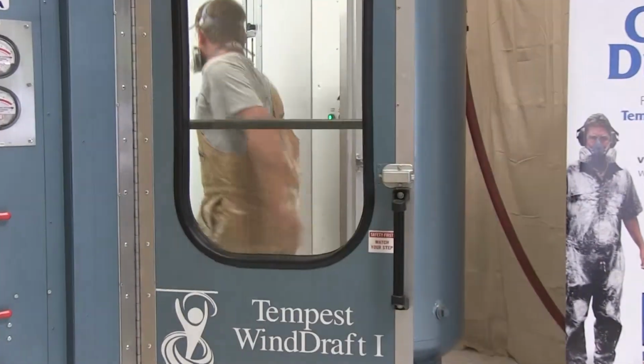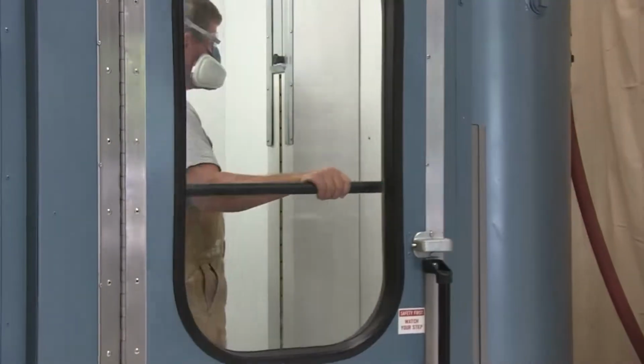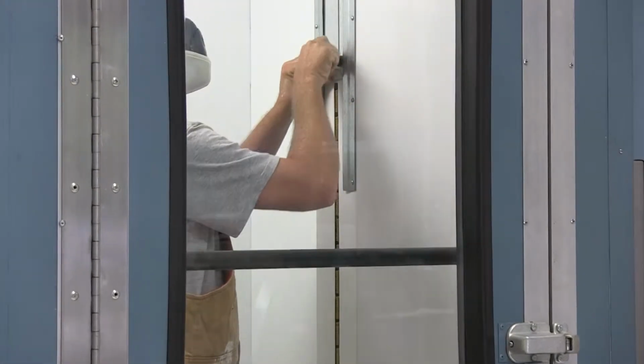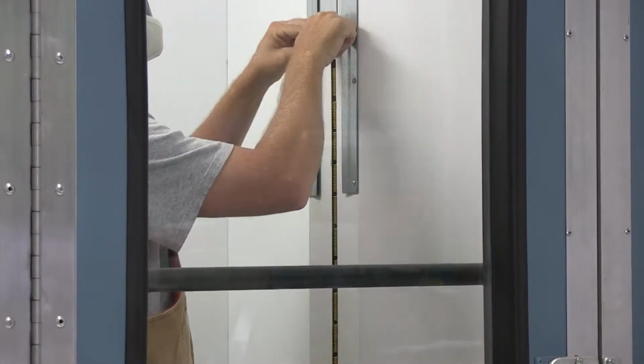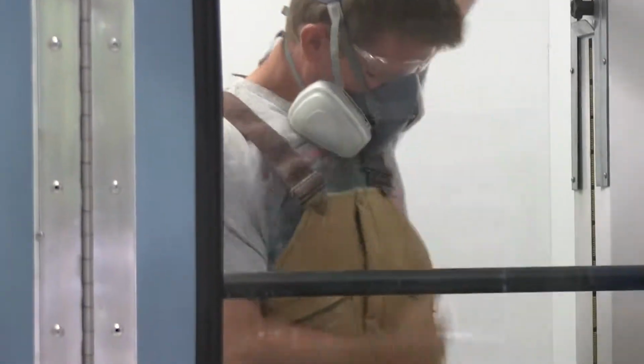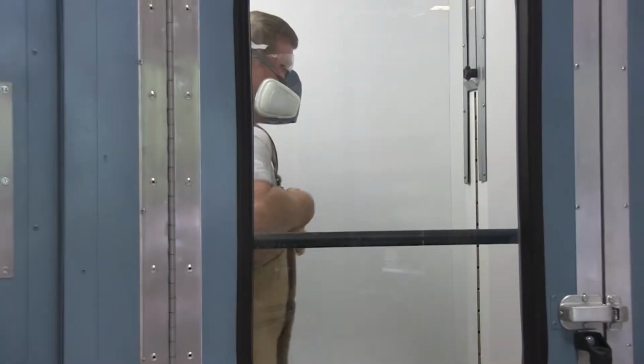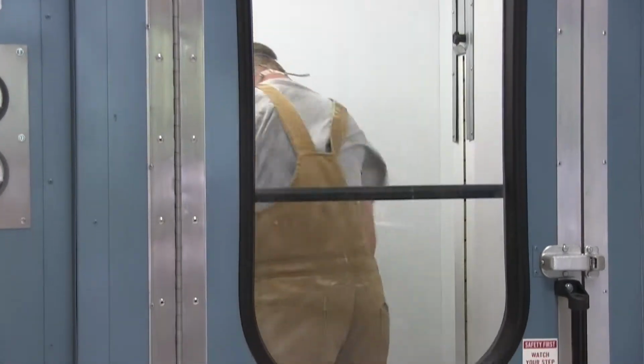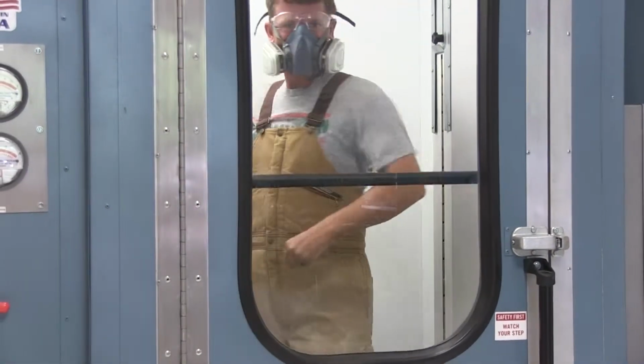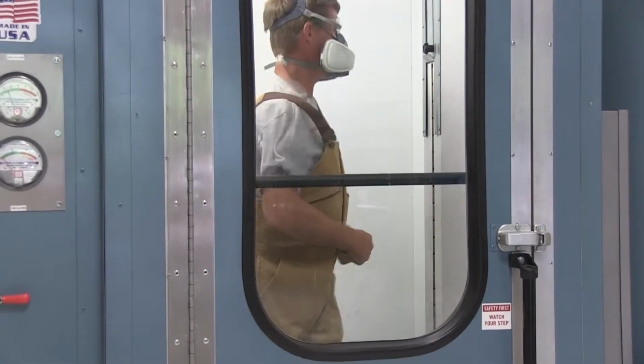Our cleaner is a low-pressure air system with 2 separate directional airflows to remove the dust from a worker's clothing. Wind is a horizontal stream of air regulated to less than 30 psi. The liberated dust is simultaneously captured in a vertical flow of air, the draft, for immediate evacuation from the booth and the worker. The air enters the booth through an open grate above the door and flows down through the booth, exiting through the bottom and back wall.